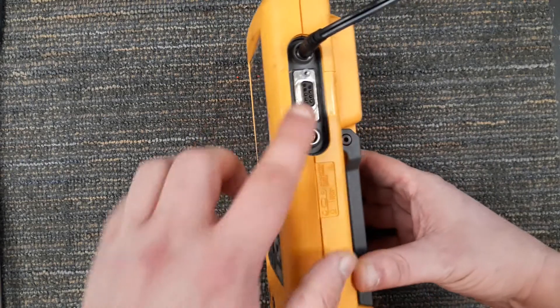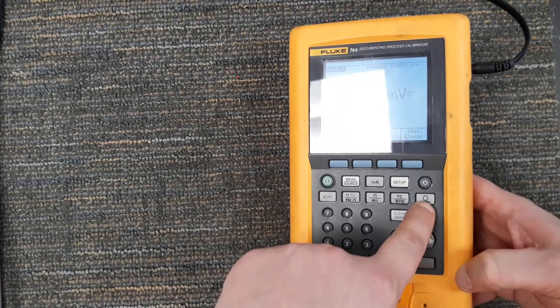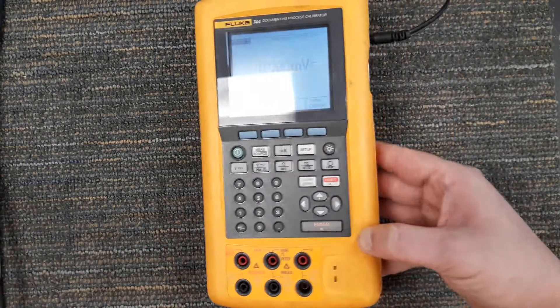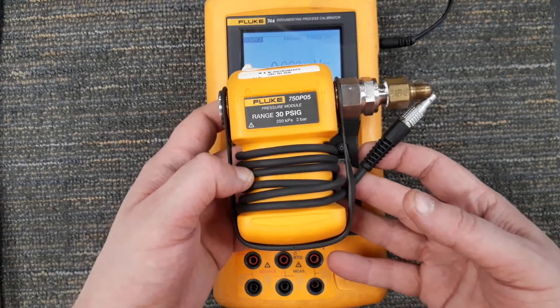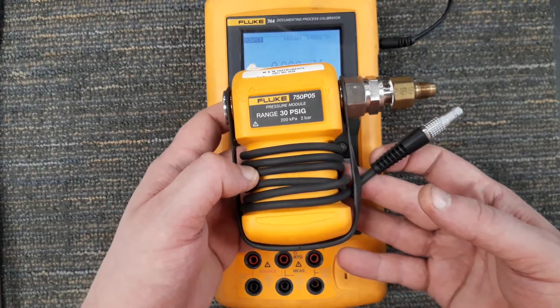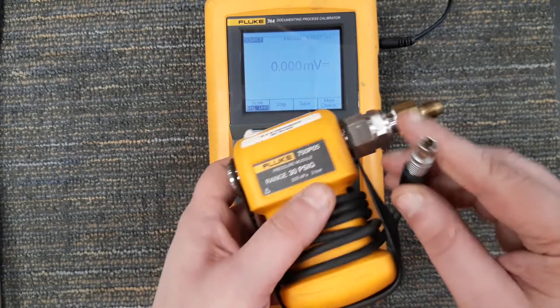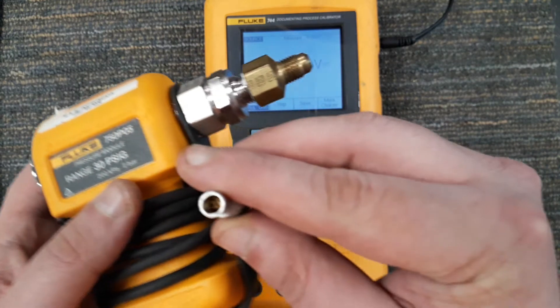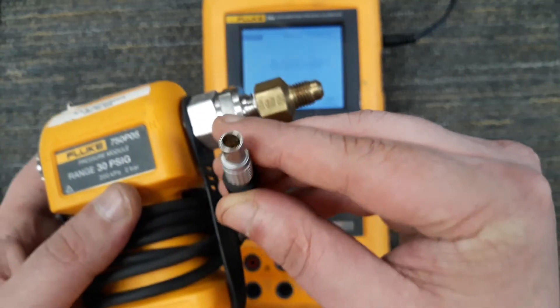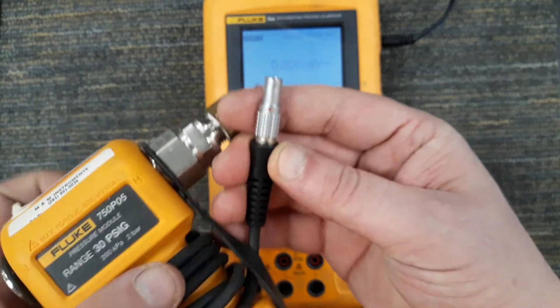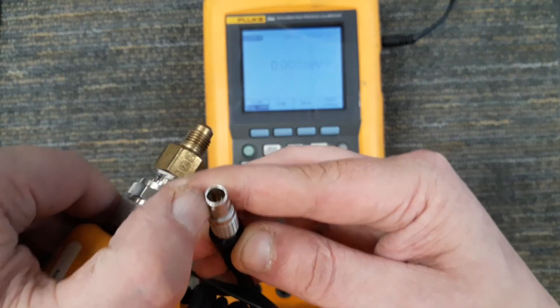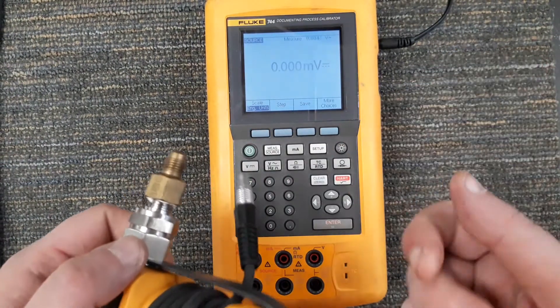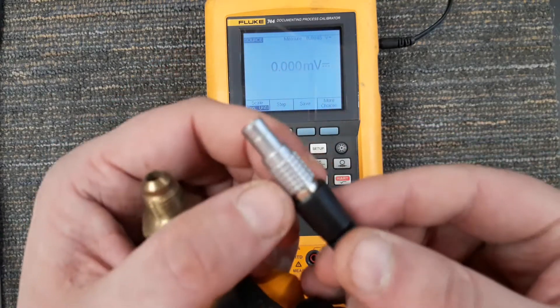We're going to look at the side of this. Again, I've already pointed out the power jack. This right here is going to be what's used in conjunction with our pressure, which you need an external pressure module. In this case we have the Fluke 750 P05. It has a range of 30 psi. If you look in here you can see there's five pins in there. If you look on the side, if I rotate this around, see that's got a red dot - it's keyed. These pins need to go in a very specific direction.